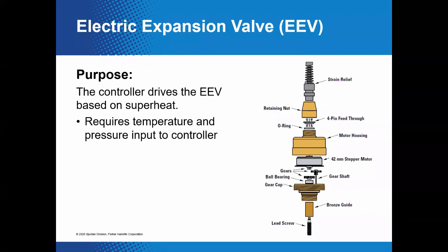Part of this assembly is often referred to as a digital linear actuator, and when we go over to our manufacturing plant, they talk about DLAs all the time, and I thought that was some kind of position that the major leagues were going to start to use to facilitate the game. That's not what that is. Nope. In essence, the DLA converts the signal from the controller and turns it into a linear movement of the pin as it interacts with the port, and ultimately controls superheat in this application.